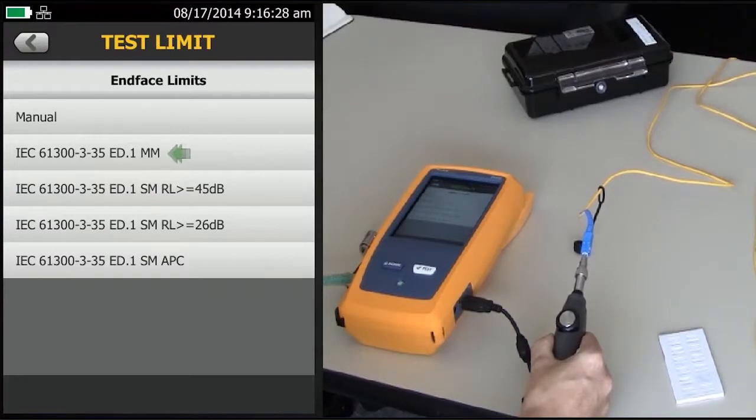The first one is for multi-mode, whether it's field polished or factory polished. The second one here is for single mode, and that's if it's factory polished. The third one here is for single mode again, but that's if you're doing a field polish. And then finally, we have the APC, the Angled Physical Contact Connector.